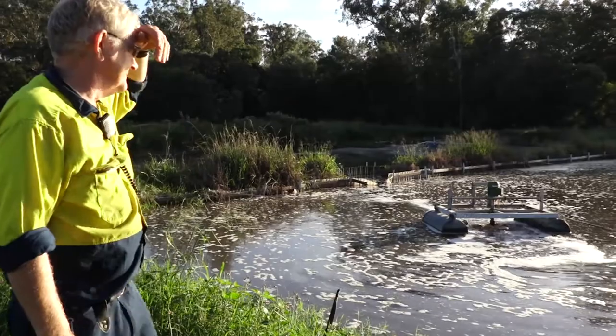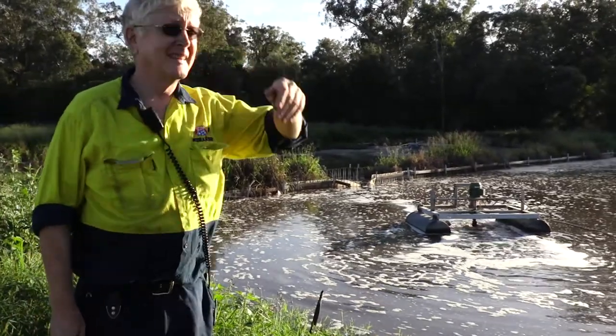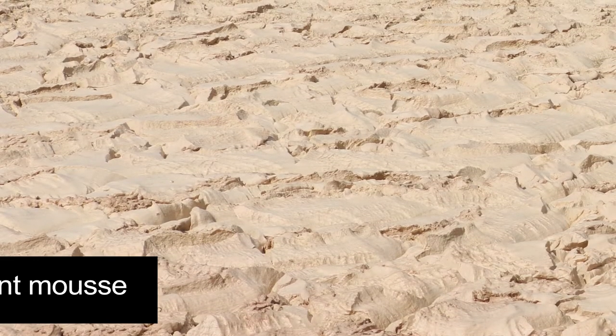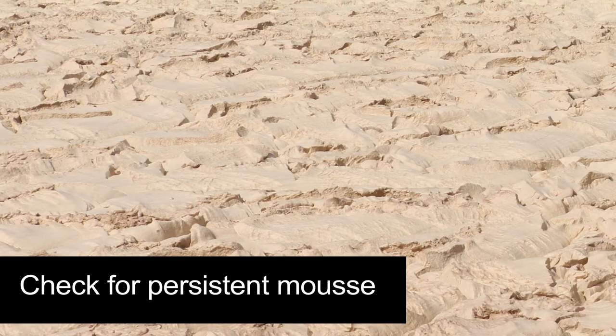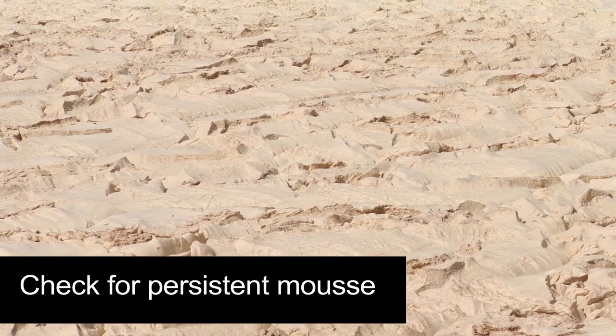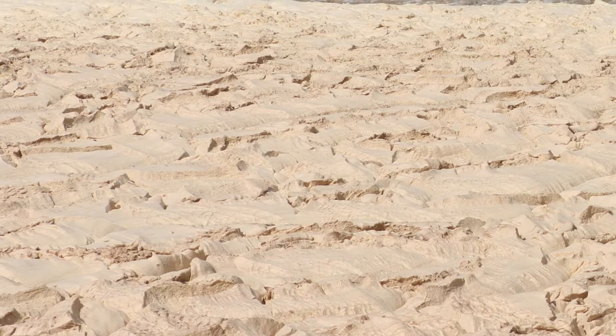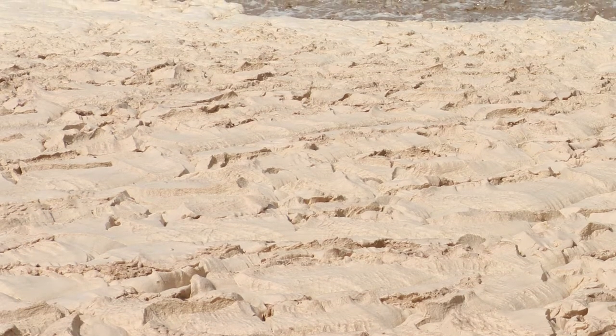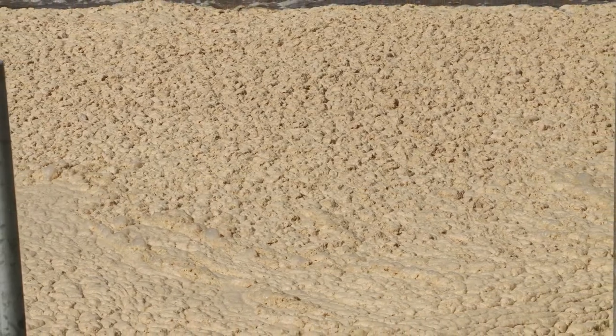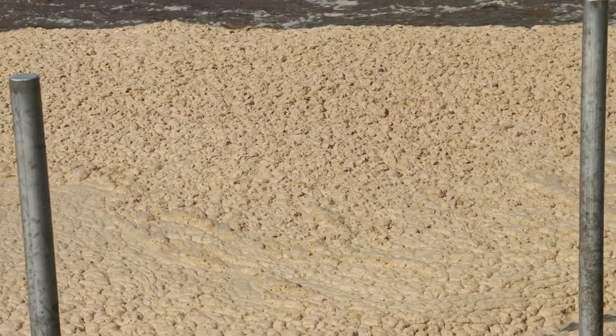Operators need to watch for various problems in aerobic ponds. If there is any sign of a persistent white Pavlova mix style mousse that often looks like fat, seek urgent appraisal by an expert. Foam is often noticed prior to a rain period when atmospheric pressure drops. This may indicate a pond operating close to its limit.